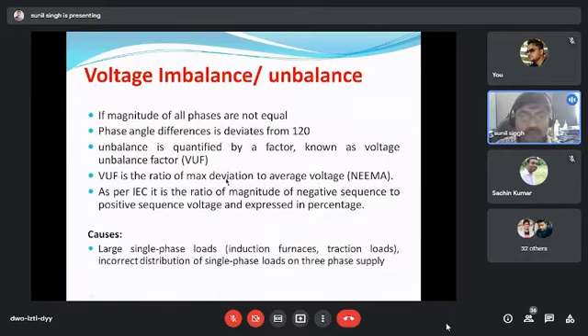Or what is the maximum deviation? Maximum deviation from the average. So it is the maximum first phase deviation of the average voltage. Take the second phase, third phase. What is the maximum deviation? We'll take the numerator and write the denominator. Average voltage multiplied by 100 will give you the voltage unbalance factor in percentage.